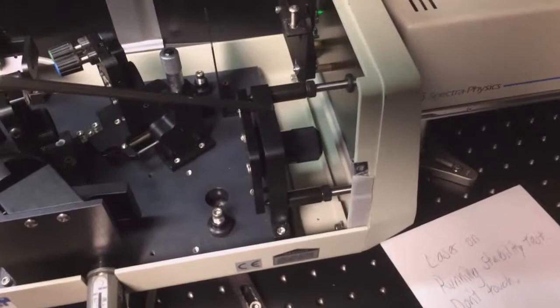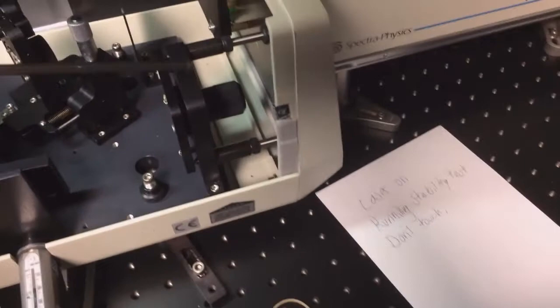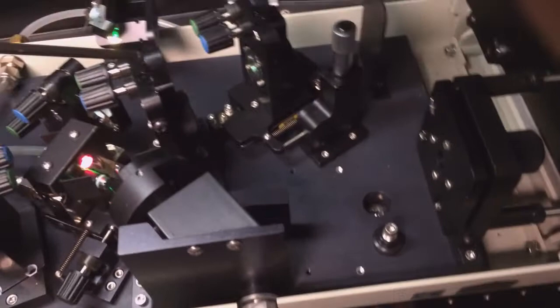The fluorescence will hit this spherical mirror here, which will then go through a filter and be reflected off of the back reflector. And this is one of the mirrors that is tunable on the backside when the laser is closed. That is used for daily optimization of the output power.